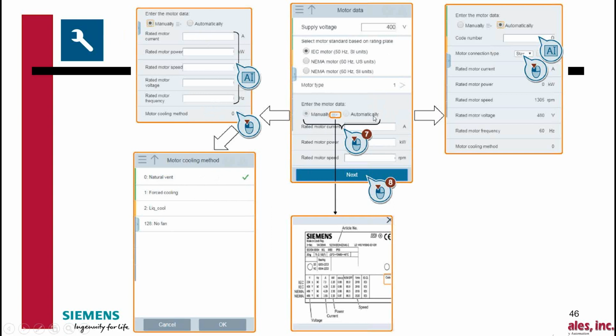If you select automatic, it's going to look for the part number of a Siemens motor and populate this information based on that part number. There's a catalog in the drive that knows these Siemens motors. So with manual, you enter data off of a motor nameplate, whereas with the other, you just pick the part number and it populates automatically. I assume most of you are not going to have Siemens motors, so we'll just do the manual, and that's what I'm going to step through in the example.